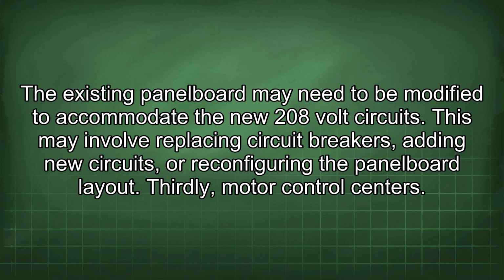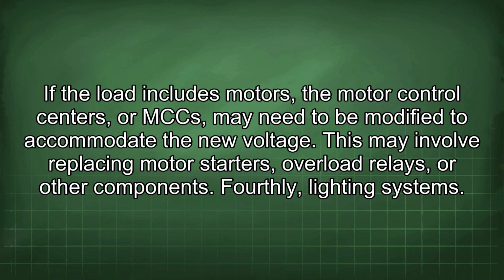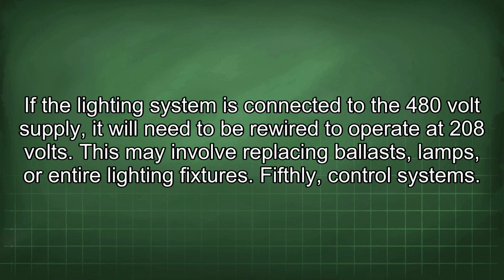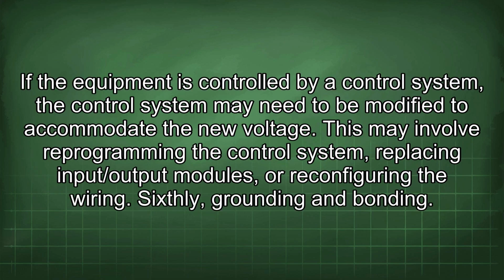Thirdly, motor control centers. If the load includes motors, the motor control centers, or MCCs, may need to be modified to accommodate the new voltage. This may involve replacing motor starters, overload relays, or other components. Fourthly, lighting systems. If the lighting system is connected to the 480-volt supply, it will need to be rewired to operate at 208 volts. This may involve replacing ballasts, lamps, or entire lighting fixtures. Fifthly, control systems. If the equipment is controlled by a control system, the control system may need to be modified to accommodate the new voltage. This may involve reprogramming the control system, replacing input/output modules, or reconfiguring the wiring.